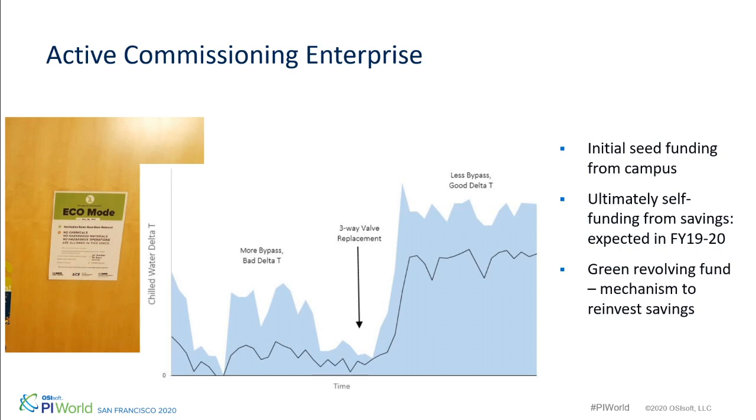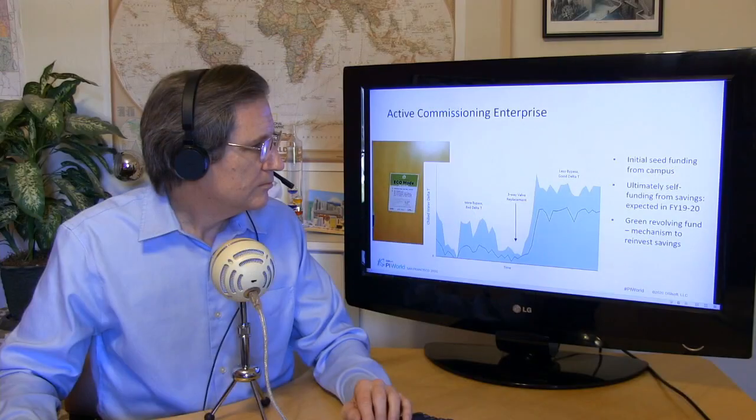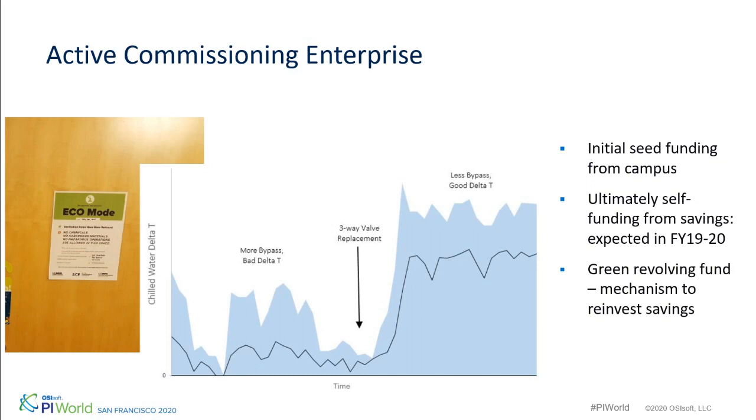Now, you were saying that this type of comparison was just something you weren't able to do in the past. Yeah, that's correct. Just having a single view of all the buildings, delta T and flow, and then how the plant is behaving as a result was not something we were able to see before. So the power really is for the plant. If the chiller is not running efficiently, the plant can then identify why, whereas previously it was a total black box.